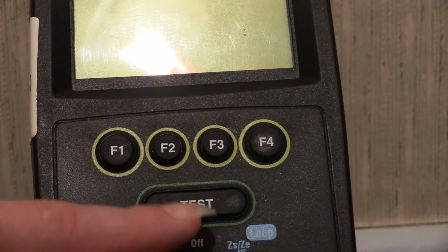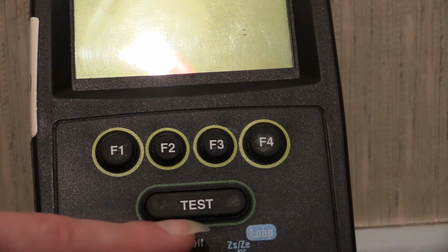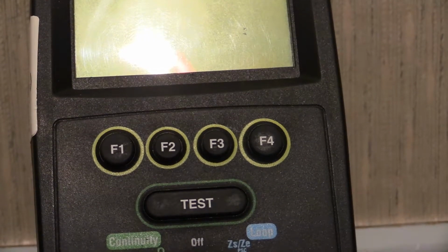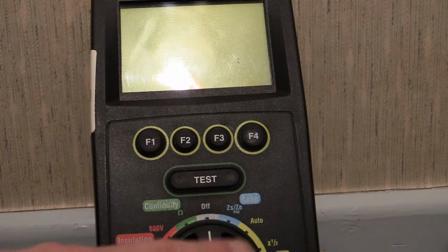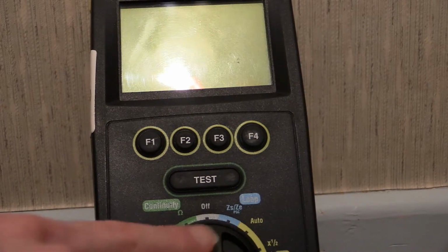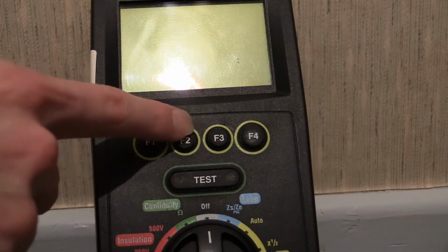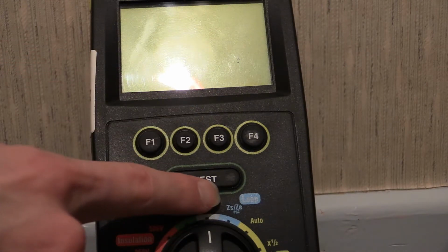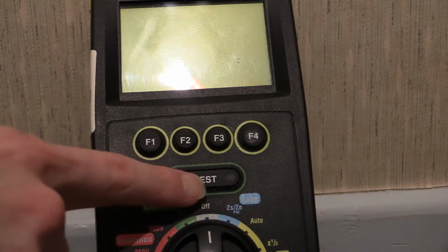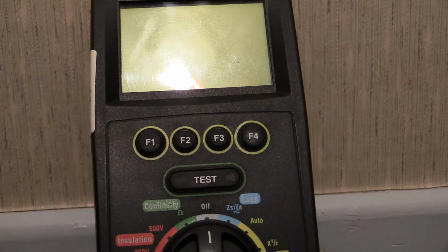So again, if you're doing an RCD test, you can turn it on auto. If I just zoom that camera out a bit. Okay, there's the auto down there for the RCD test. You can turn this round to auto, press F2 and then press test, and because you've locked the test button in, the RCD test will go through all of the tests. It saves you having to walk backwards and forwards from this to the consumer unit to reset the RCD each time, because in the auto mode there are a series of tests where it will trip the RCD multiple times.